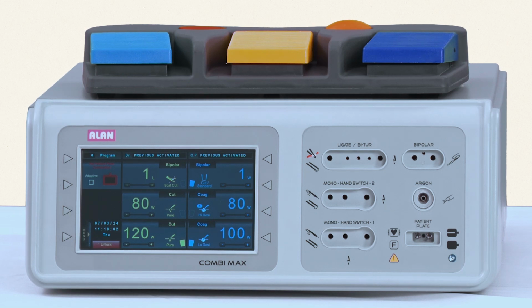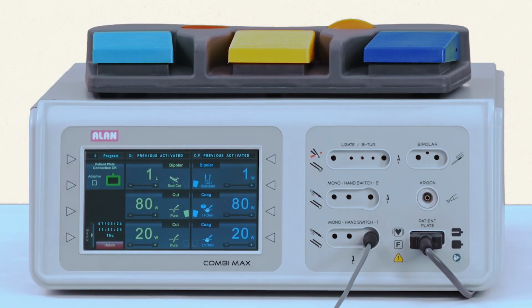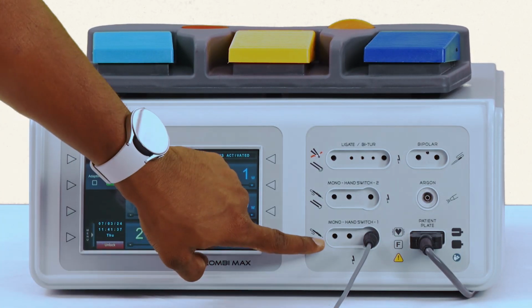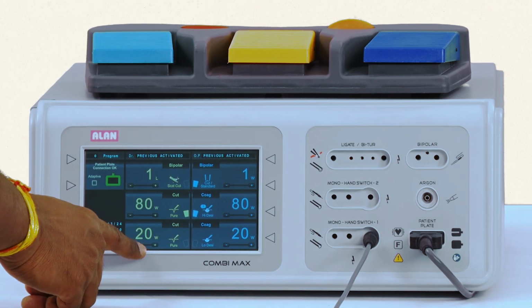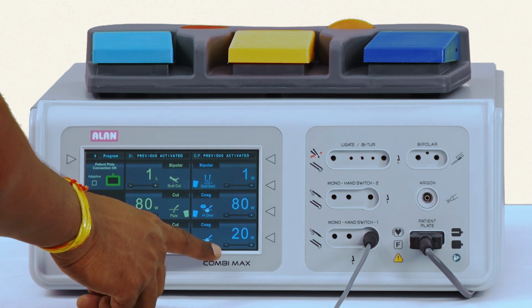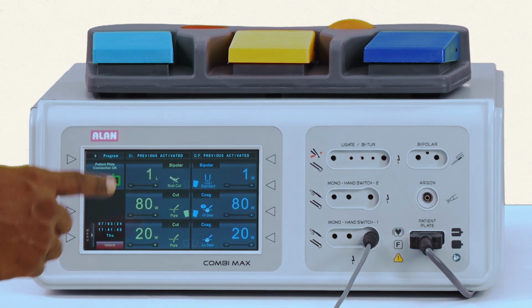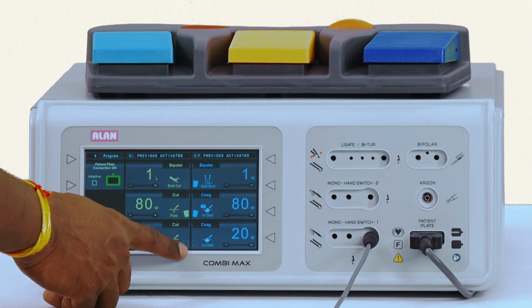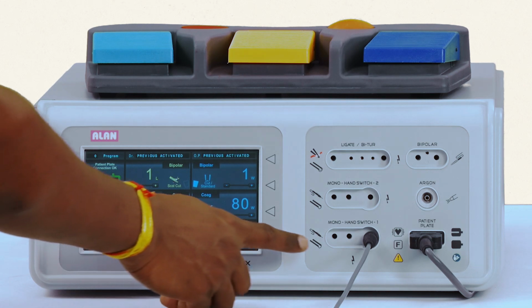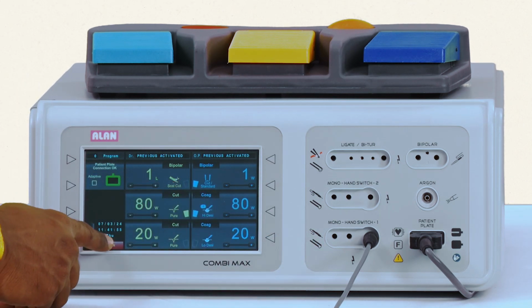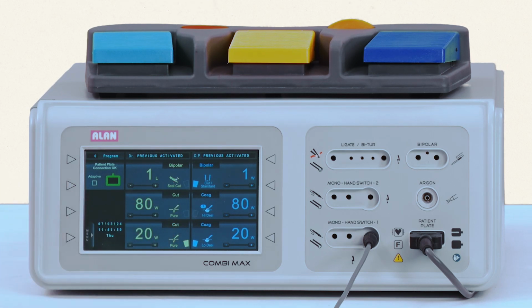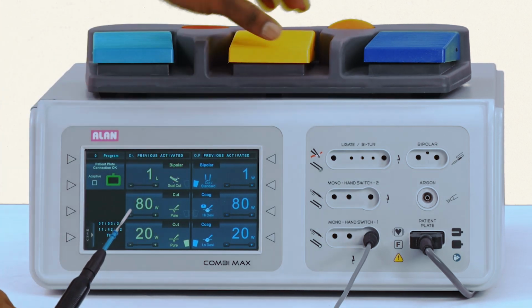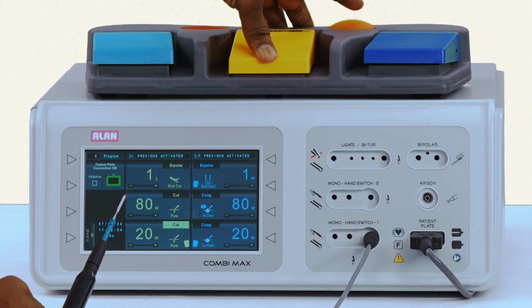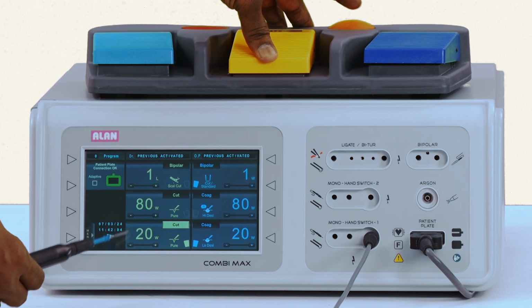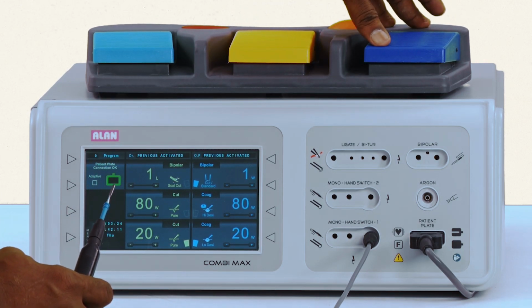Let's see some examples in which I will show you how to connect hand operated pencil and foot operated pencil in these ports. In example 1, we have connected a foot operated pencil in mono hand switch 1. Now you can choose your desired cutting and coagulation mode with wattages, and before activating, make sure this foot pedal icon should be in the respective row. For example, we want the output from this receptacle, so I will choose here. Now this will glow. See that? When I press cut, this glows. That means this segment is getting activated.